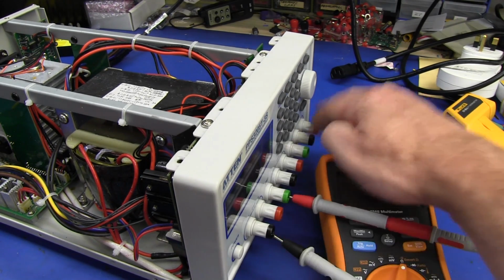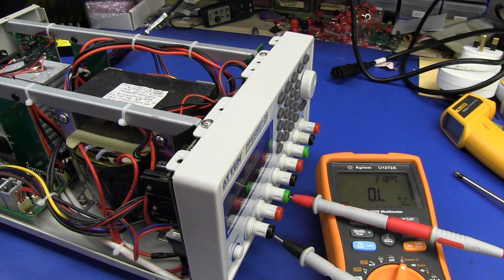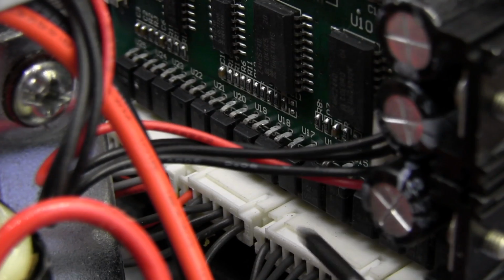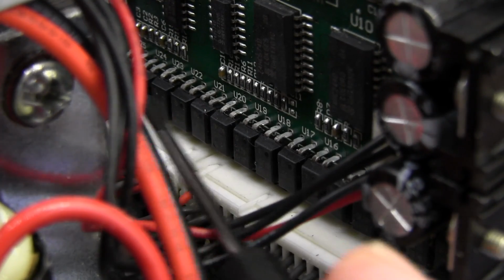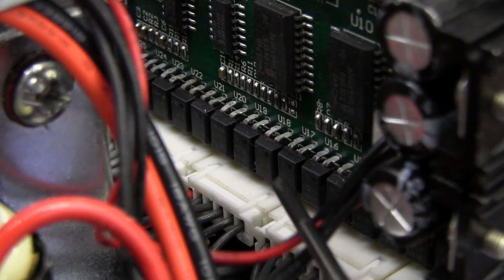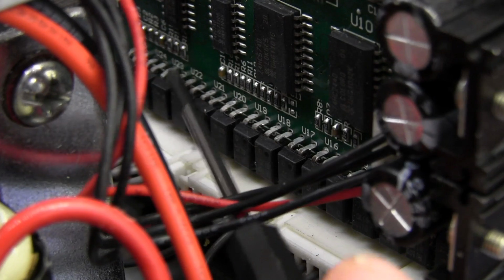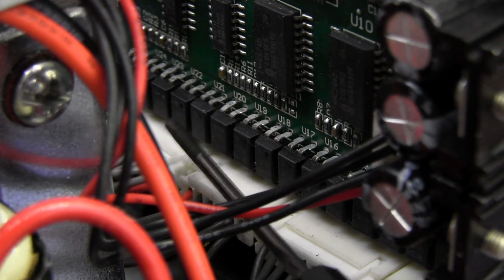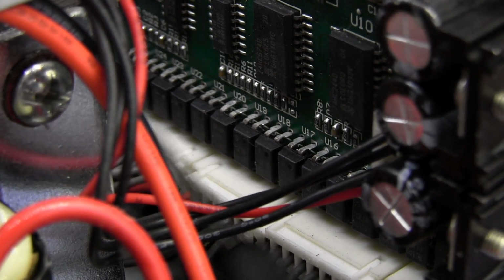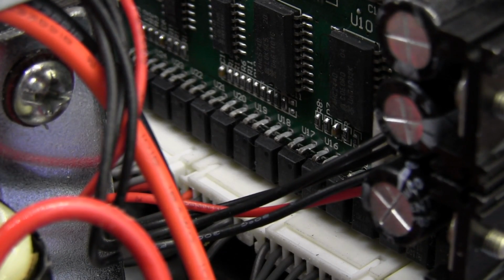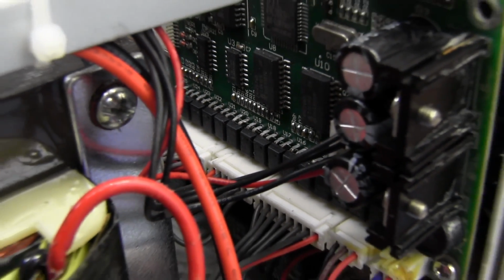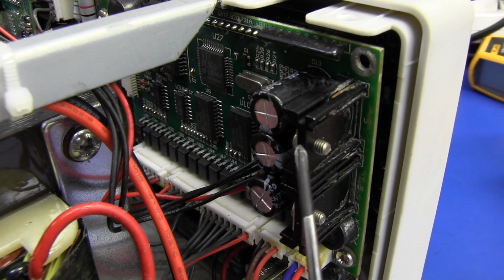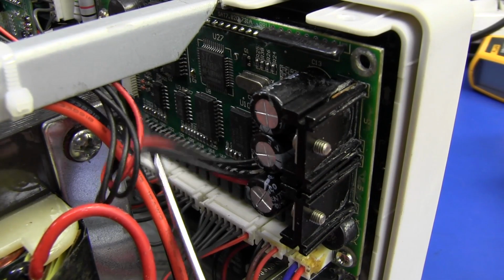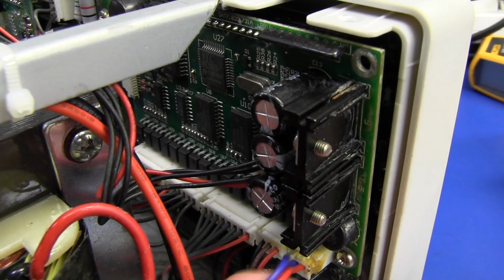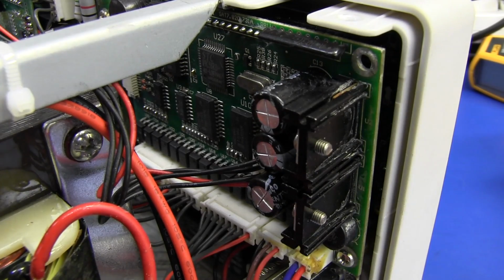The actual voltage output terminals are completely isolated with their own taps and their own logic, and we'll find the opto isolators are actually on the logic board. And there they are, as you can see, and that, folks, is a lot of opto isolators. They go all the way across the bottom of the logic board, because you need to have multiple serial interfaces to all three of the isolated channels. So that's why we've got three separate connectors there with the data going out. So there's a ton of isolation there. And of course, that logic board on the front panel has its own onboard regulation. It's got its own transformer tap coming off. Yep, there it is, own transformer tap down there, which powers all the logic.